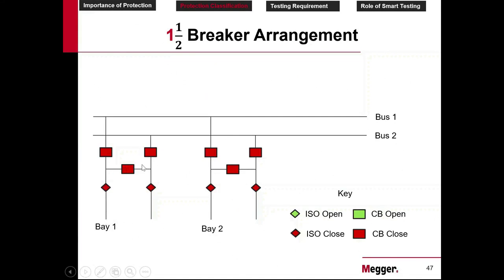So it's actually a parallel path. Supply goes to bus 1 as well as bus 2. It comes from bus 1 as well as bus 2 like this. Now let us create a fault in bus 1. Same fault. What happens? Which breaker should we trip? From the drawing, you can see that all the breakers connected to this bus 1 should trip. So it will trip in this manner. The relay will be designed to trip these 2 breakers.